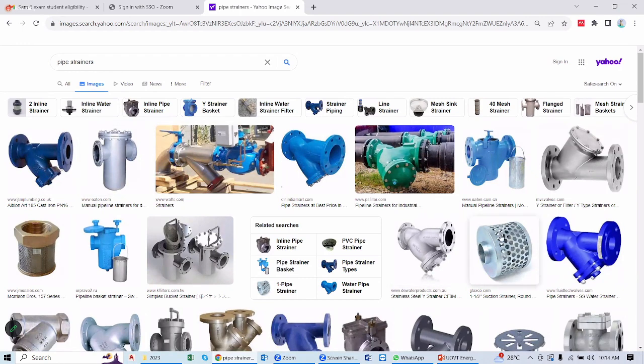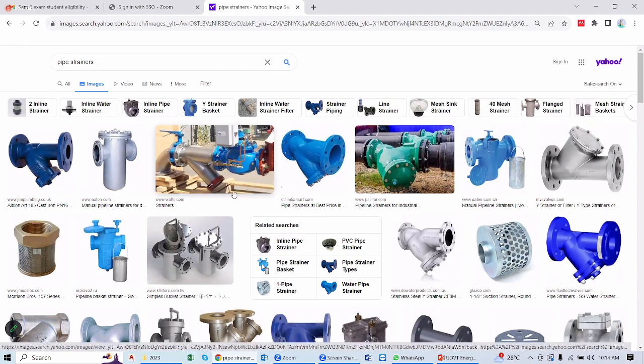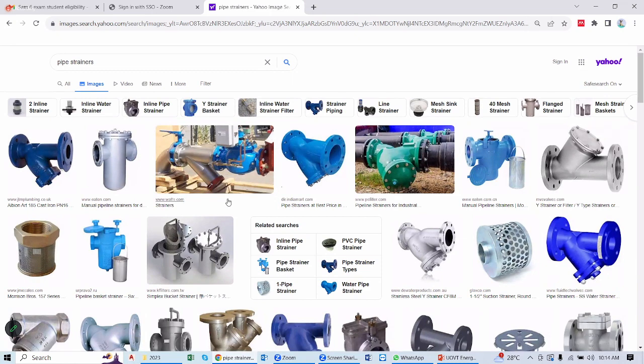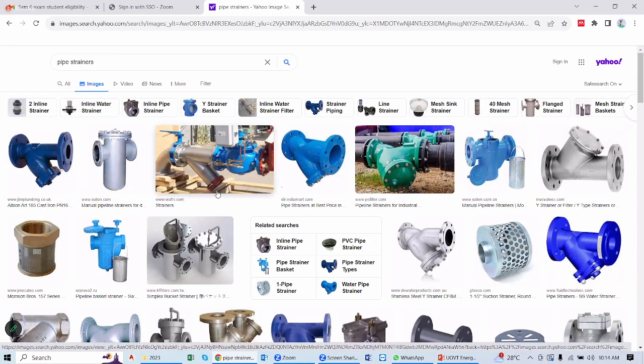But the risk is you get this type of a filter inside, and you can remove these nuts and take it out. And the risk is if they are clogged, then the pump is actually sucking air, which will be difficult because of the clog. So that is very dangerous.